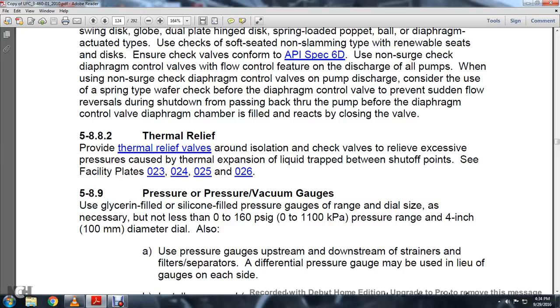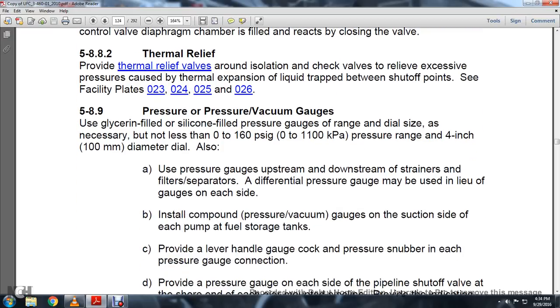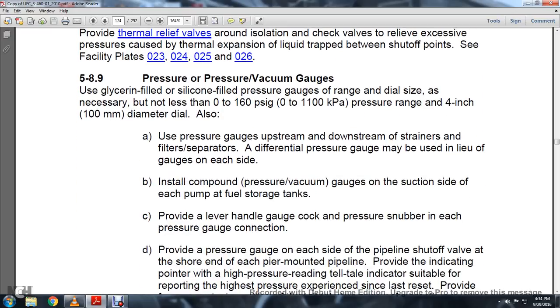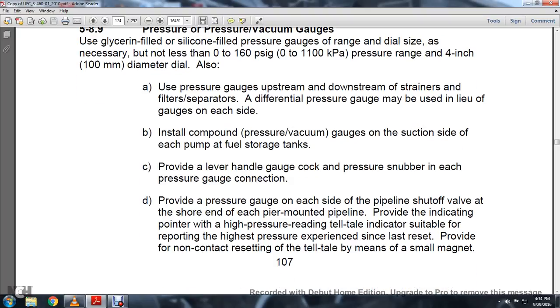Use glycerine-filled or silicone-filled pressure gauges, with a range and dial size as necessary but not less than 0 to 160 psi and a dial diameter of 4 inches. Also use pressure gauges upstream and downstream of the strainer and filter separator. Differential pressure gauges may be used in lieu of gauges on each side. Install compound pressure-vacuum gauges on the suction side of each pump from the fuel storage tanks. Provide a lever-handle gauge cock in each of the pressure connections.